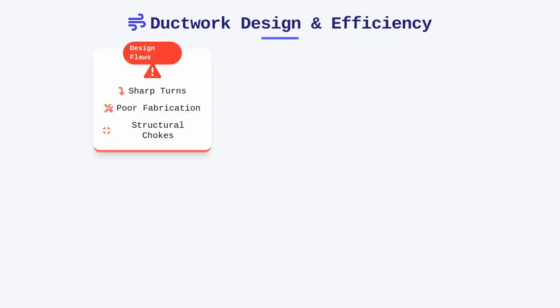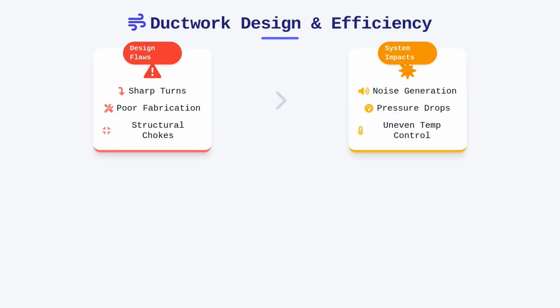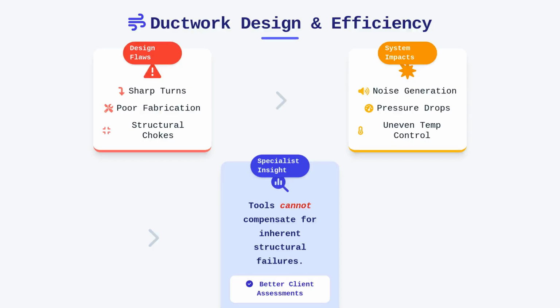The design of the ductwork directly influences every bit of the efficiency we have discussed, as every transition introduces potential energy losses. When air encounters a sharp turn or a poorly fabricated takeoff, it experiences sudden pressure changes that can lead to noise, velocity dead zones, and uneven cooling or heating. As specialists, we must recognize these design limitations because they dictate how difficult a system will be to clean effectively. Even the most powerful vacuum or agitation tool cannot compensate indefinitely for a system that is inherently choked or structurally compromised. Recognizing these limitations puts you in a superior position to provide accurate assessments to your clients regarding what cleaning can and cannot achieve.